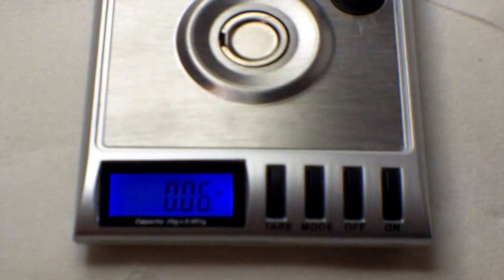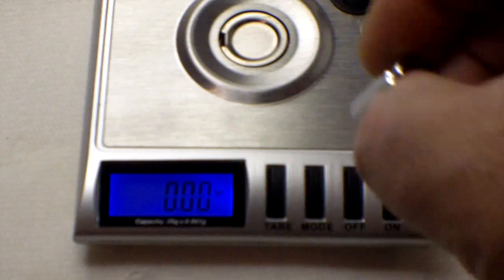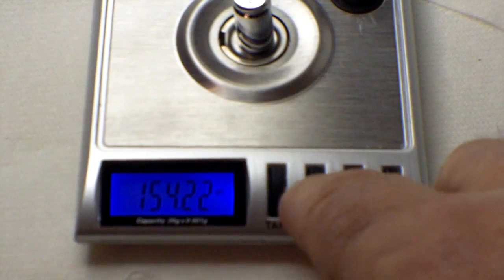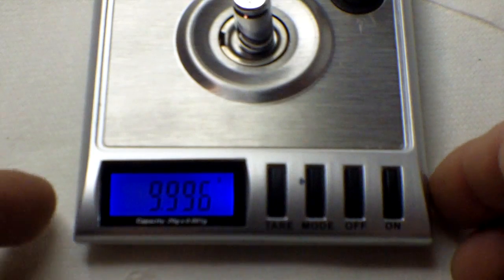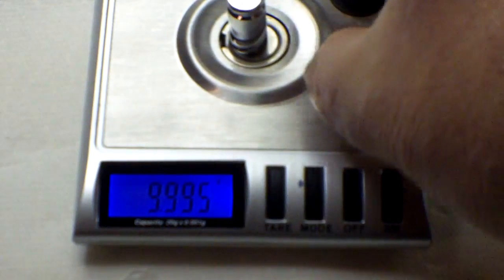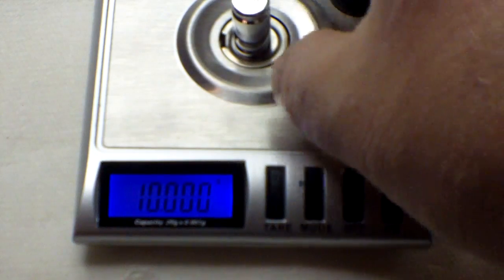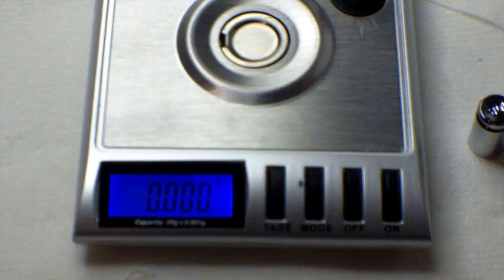Put this one back. Okay, so now it should be ready to weigh something. If I take a 10 gram weight and put it on here, it'll weigh 154.2 grains. Or if we switch the mode, 9.996 grams. It's a little bit sensitive to where you place it on here. There it says 10, so there is some variability in the measurement, not much. So that's how it works.